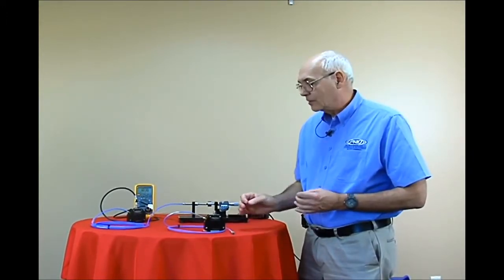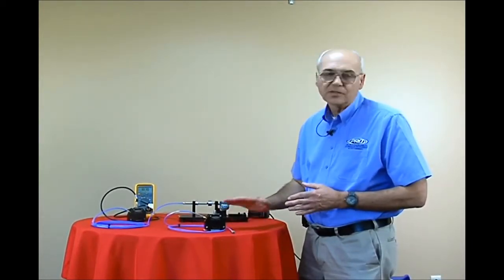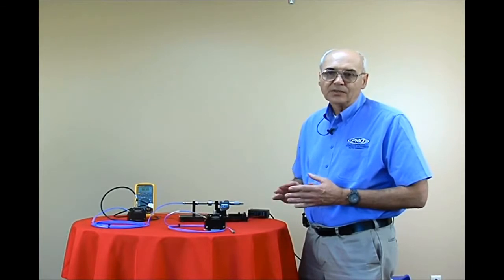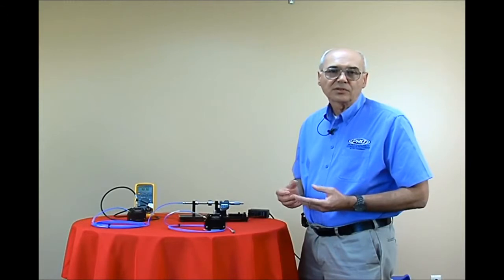We never do away with the 200 millivolts per mil. That is always there in the voltage terminals, and it's always there on the BNC. So these are just some different changes we have to make this available to process control, PLC, DCS, or SCADA systems.